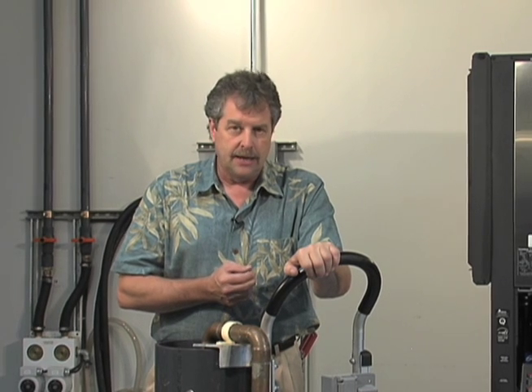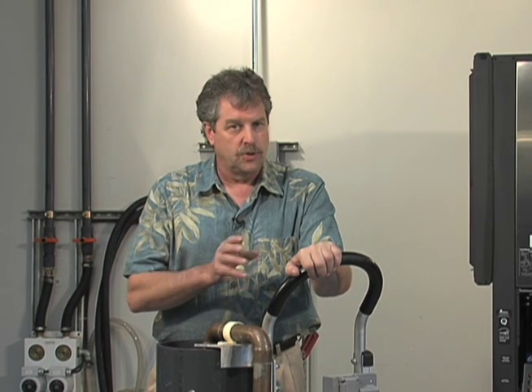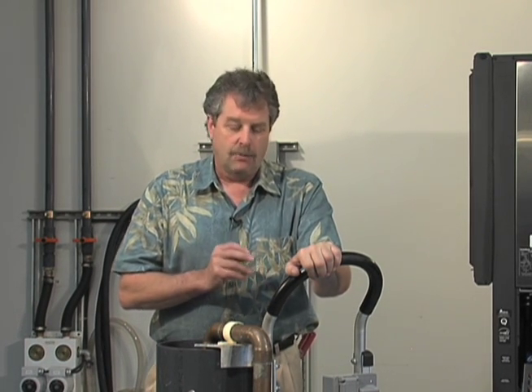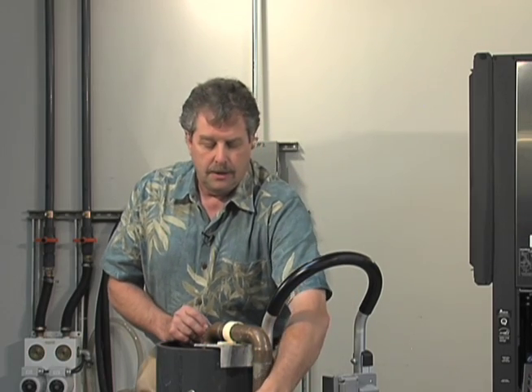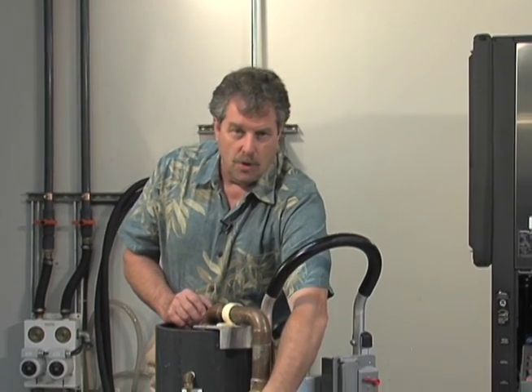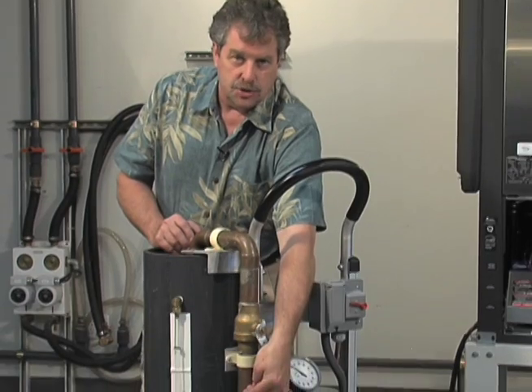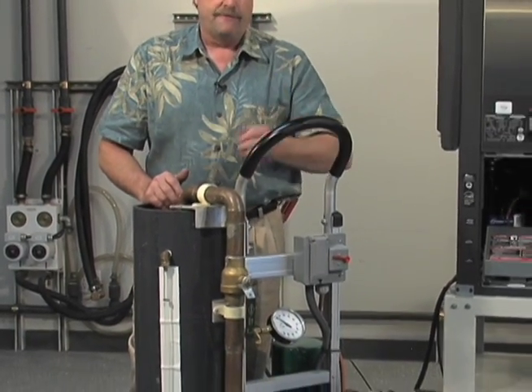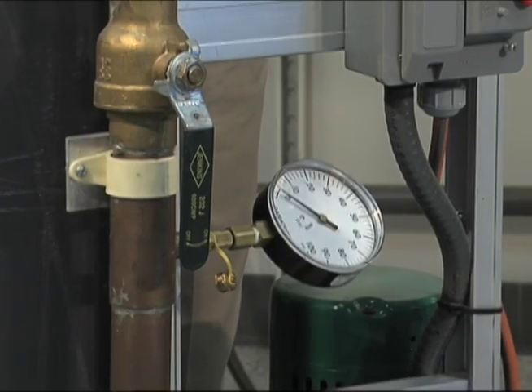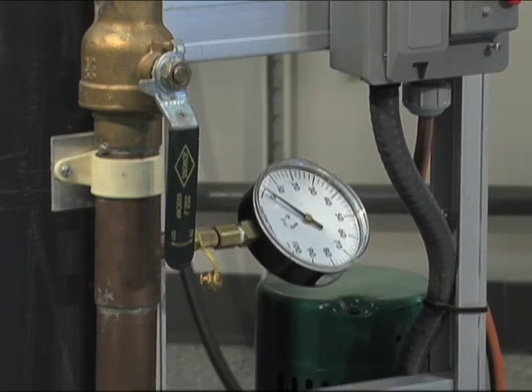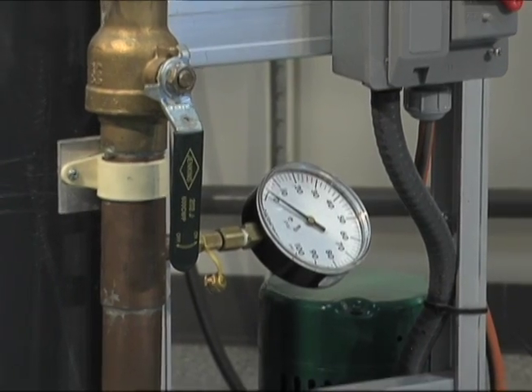And we're going to apply again those same techniques. We're going to apply some deadheading, and we're going to go ahead and see if there's any more air in that system. Again, showing the patience to verify through every step of this process that we're getting all the air out. Again, critical with a pressurized closed loop system.